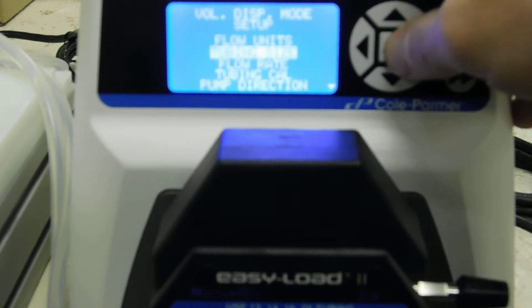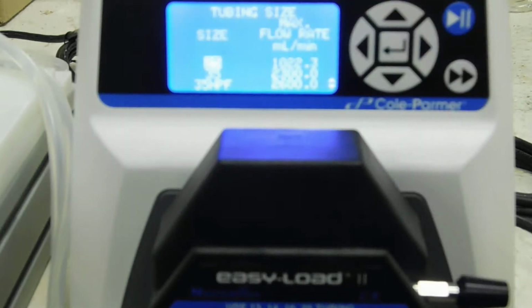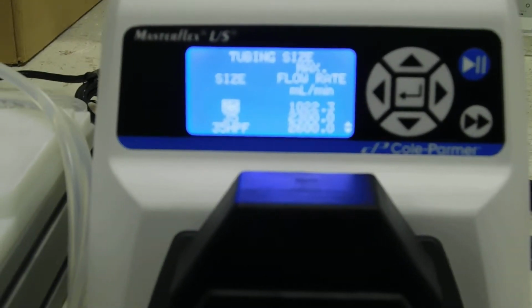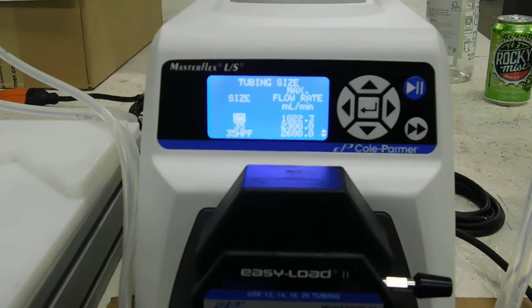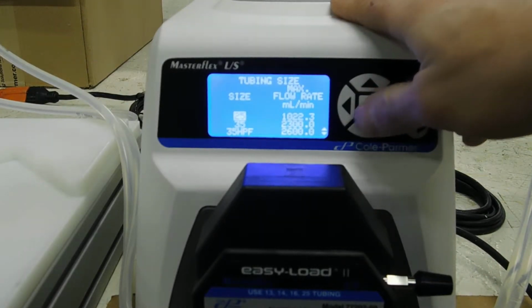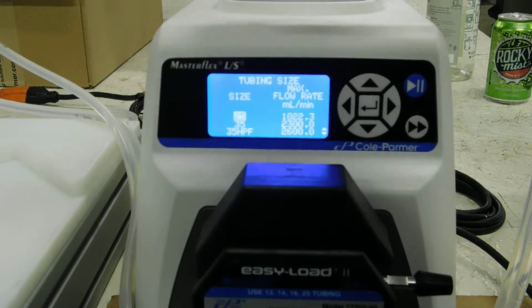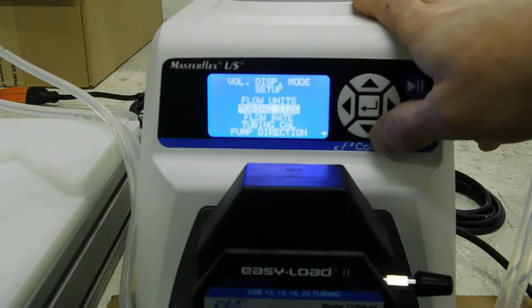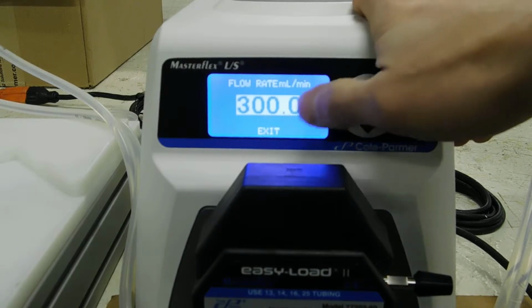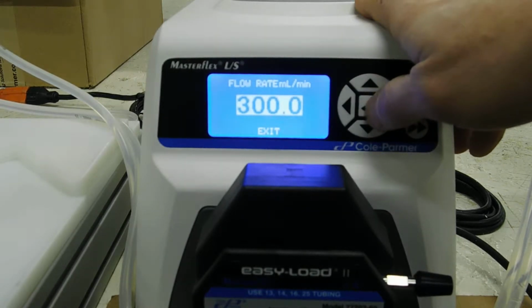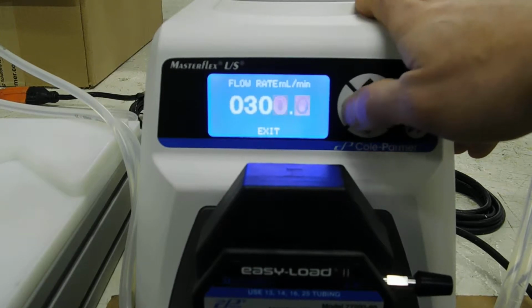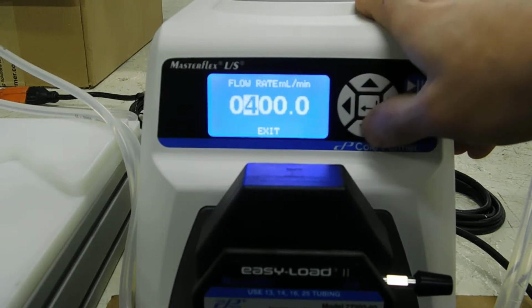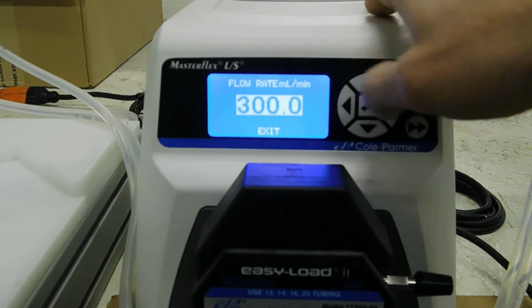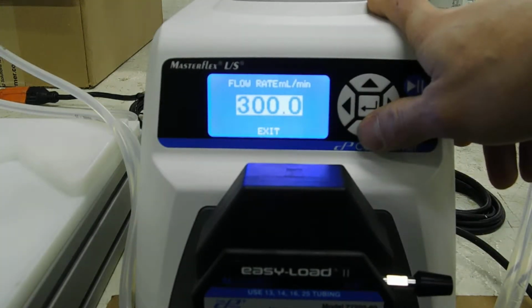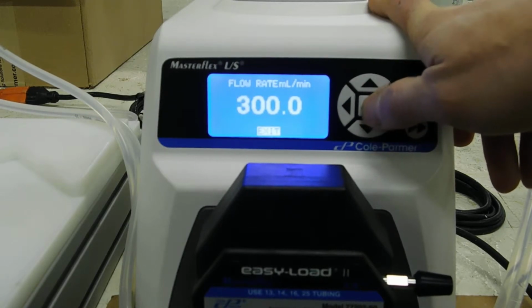Press enter. I can go into tubing size, which is the next one down, and then I can select that we're using number 25 tubing size. And press enter. The tubing size is imprinted on the side of the tubing. So if I go into flow rate, currently we are set at 300 milliliters per minute. If I want to make a change to that, I just press enter, and then I can go in and change any of these numerical values. If I press enter again, it'll box select the entire character, and then I can go down to exit.